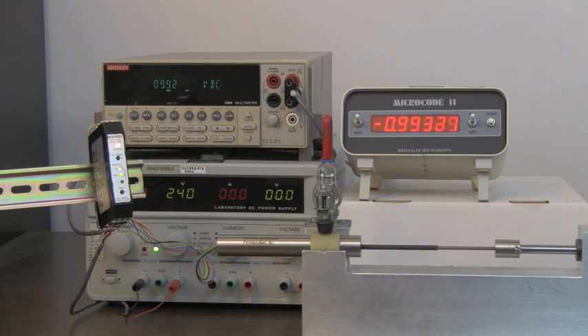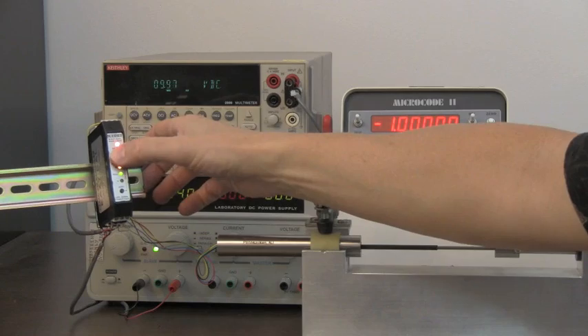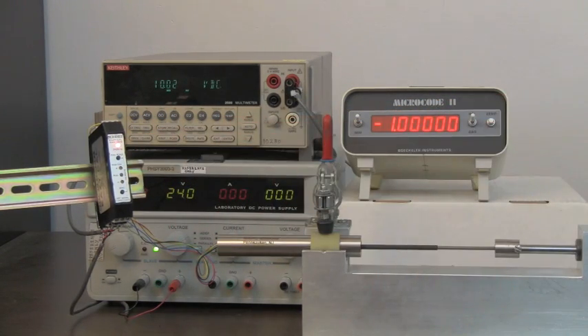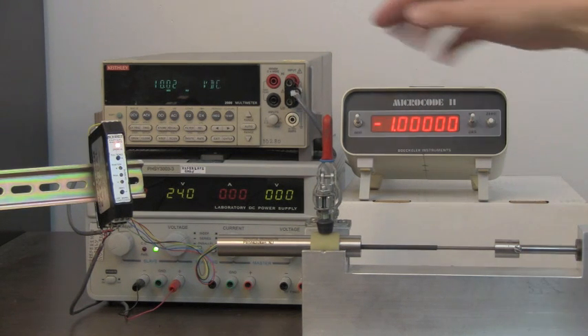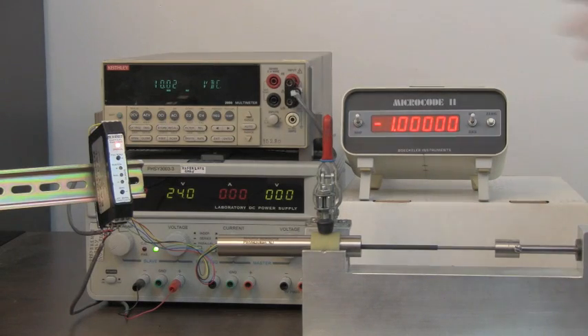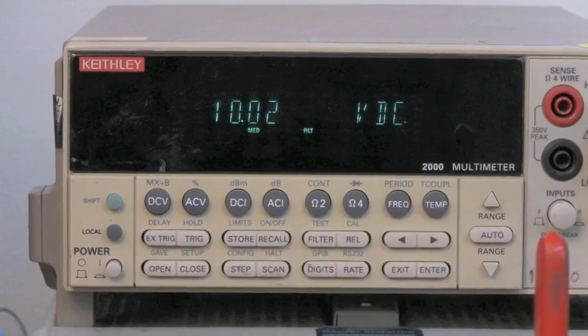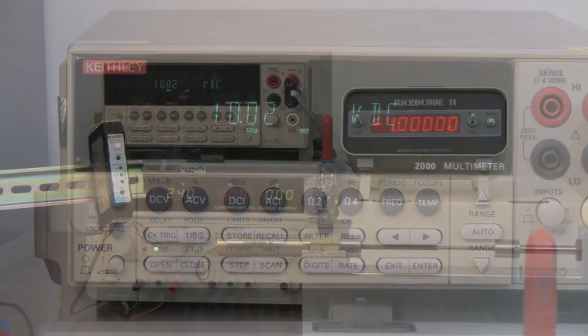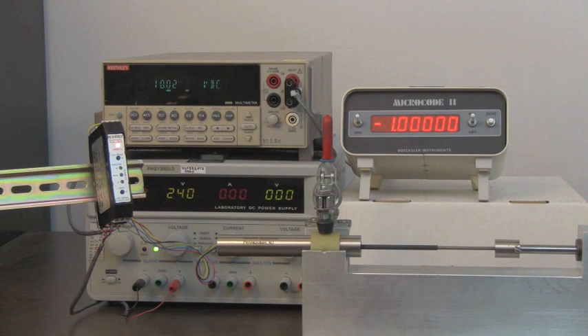When the final position has been reached, we enter the full-scale calibration point into the EAZY-CAL by momentarily pressing the full-scale push button. The positive position indicator lamp will turn off and the OpCal LED lamp will become solidly lit, indicating that calibration has been successfully completed and normal operation mode is engaged. We now observe that the output voltage of the EAZY-CAL, as displayed on the DVM, is plus 10.02 volts DC, with plus 10.00 volts DC being nominal for the plus 1.0 inch stroke position.